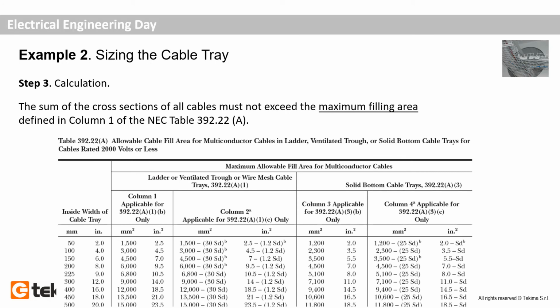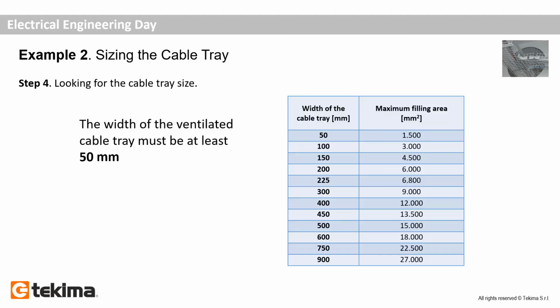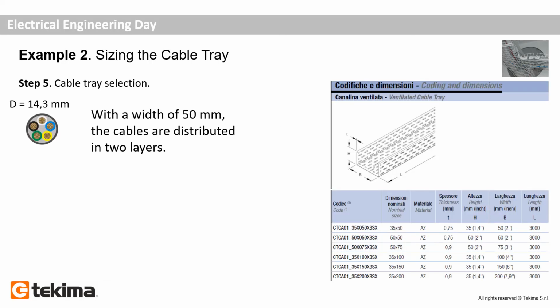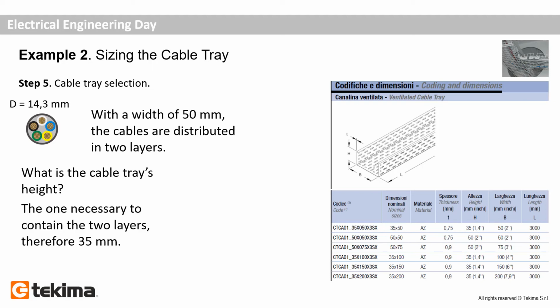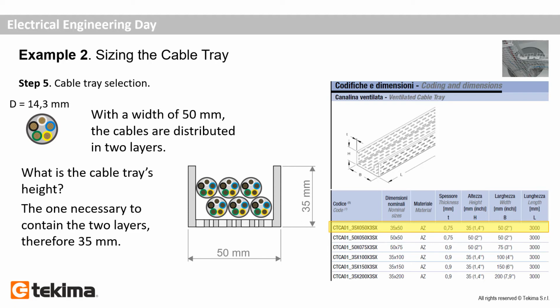Then we have to identify the maximum filling area of the cable tray. To do that, we have to look into column 1 of the table and look for the allowable filling area that can contain the cross-sectional area of the cables. In this case, 1500 square millimeter are enough to contain 963 square millimeter. This means that the width of the ventilated cable tray must be at least 50 millimeter. So let's find the product in the technical catalog of Tekima. The cables will be distributed in 2 layers, which means that the height of the cable tray has to be at least 35 millimeter, and the final solution will be a cable tray 35 millimeter height, 50 millimeter width.